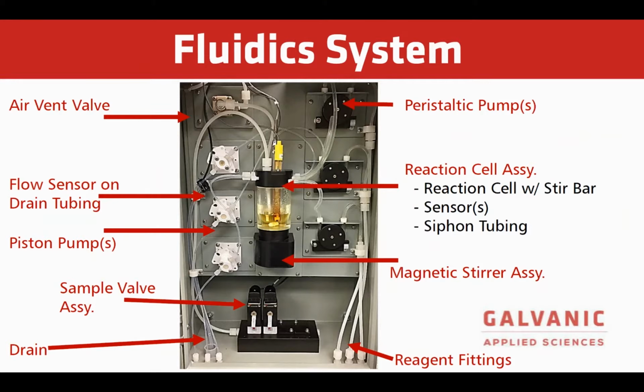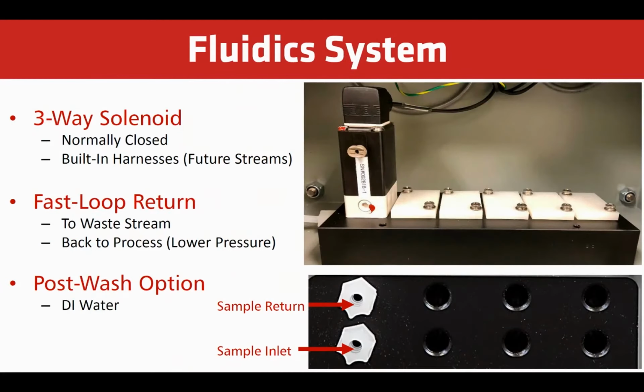Reagent fittings are also on the bottom, so your reagent containers will be stored underneath this on a shelf or on the floor. So the way that the analyzer gets a sample is you will plumb into the sample inlet, and then you can plumb the sample return back to a lower pressure portion where the sample actually originates from. And this is always fast flowing.